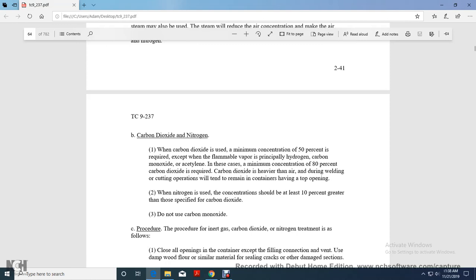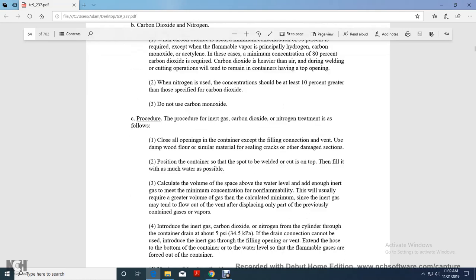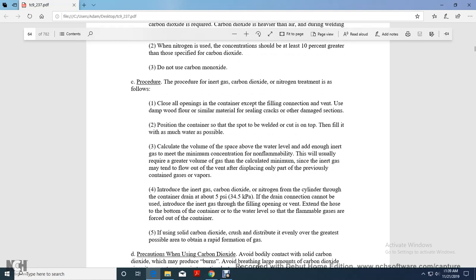Carbon dioxide is heavier than air. During the welding and cutting operation it will tend to remain in the container over the top of the opening. When nitrogen is used, the concentration should be 10% greater than those specified for carbon dioxide. Do not use carbon monoxide. The procedure for the inert carbon dioxide and nitrogen treatment is as follows.